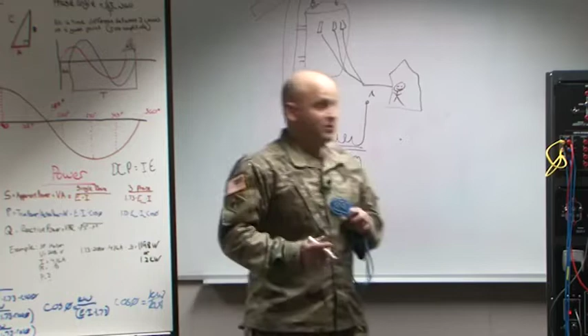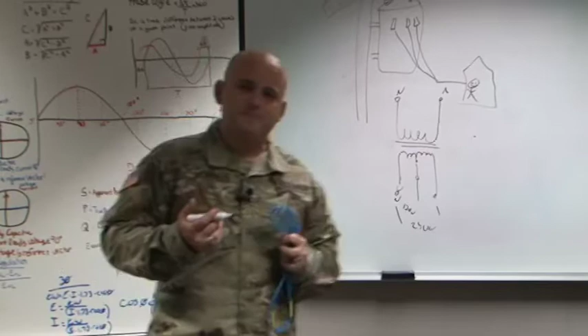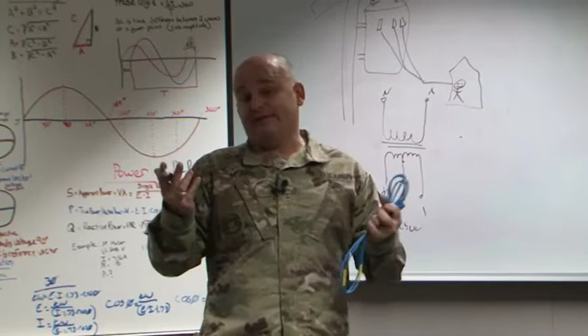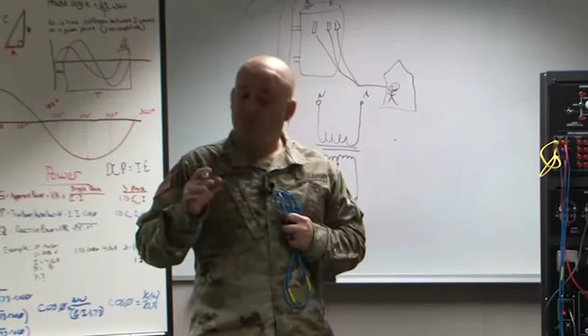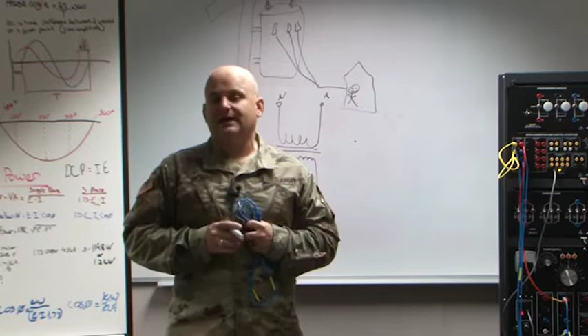So what does that mean? That means it's exactly like that little split right in the middle point between 5 and 6 over there, and that's what's going on in your house. That's how you're able to take single phase power in and get two different voltages inside your household. You might not have even known it, but the compressor in your air conditioner is more than likely running off that 220, 230, or 240. Your hot water heater, if electric, runs off the higher voltage, and your stove should too. So unless you live in a really old house, you have two voltages, and this is how you get them even though you don't have multi-phase power in your house.